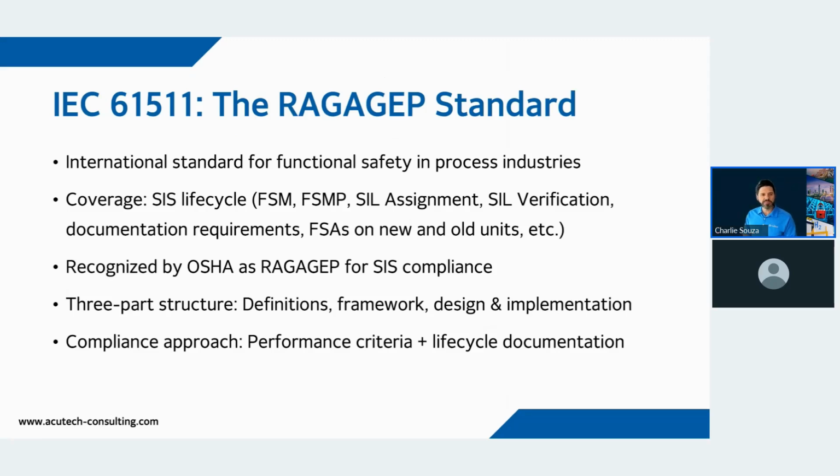We've spoken about the RAGAGEP standard. Here are just some bullet points talking about it as a performance standard. So it's not like the National Electrical Code telling you how many plugs go in the wall and how high these outlets have to be, but it will tell you that you have to follow certain steps. It may not tell you in detail how you go about these steps, but it tells you that you must follow these steps. You must look at all of them, even if some may not apply to your particular design or situation.